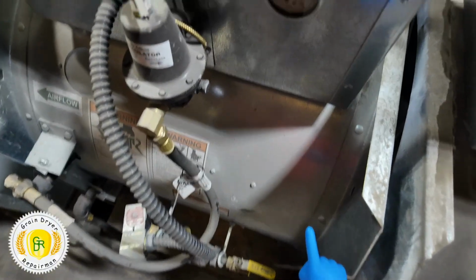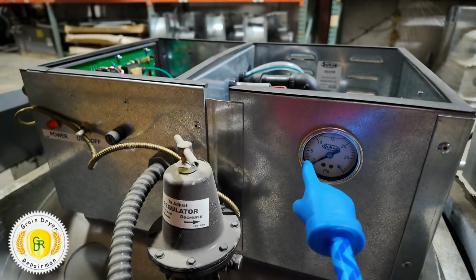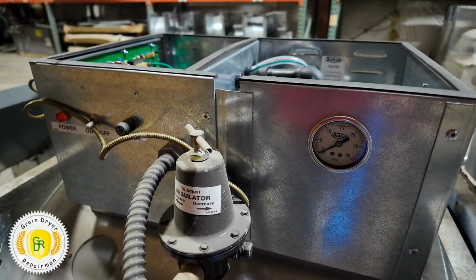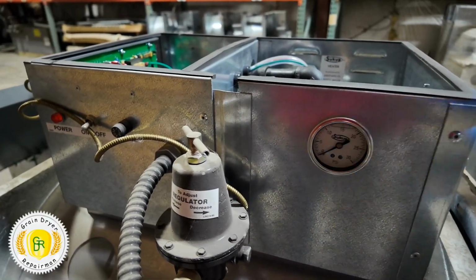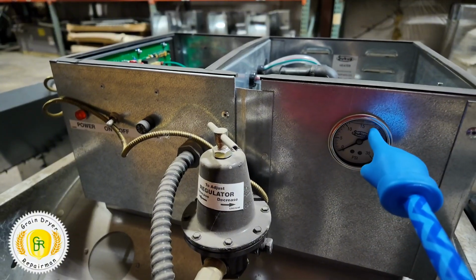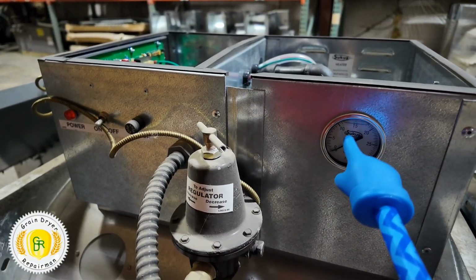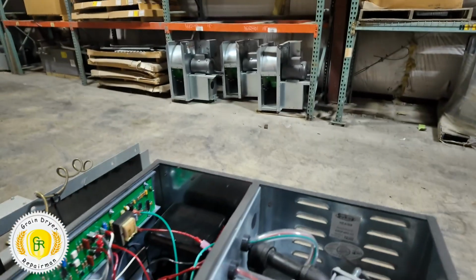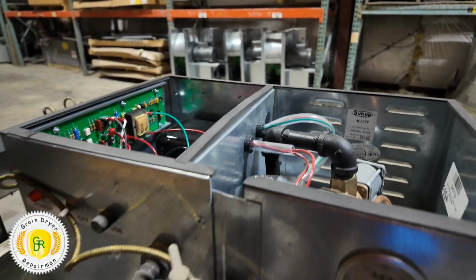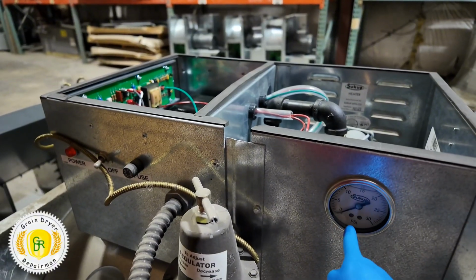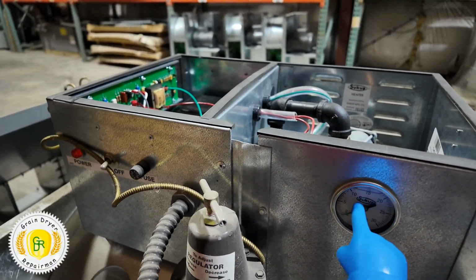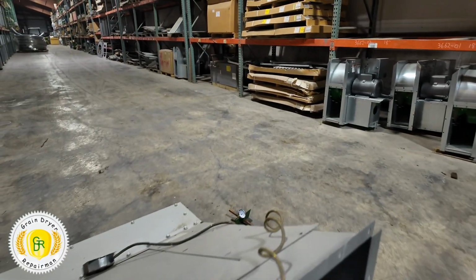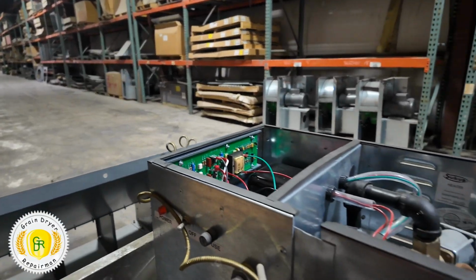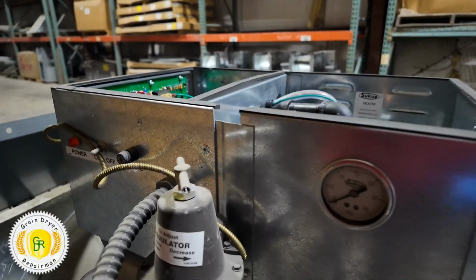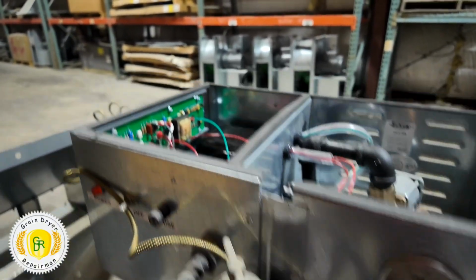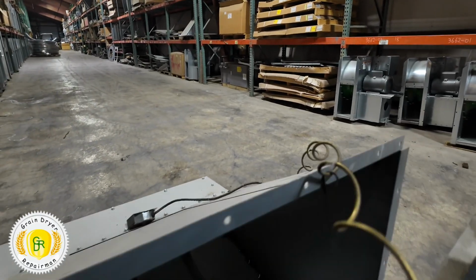What should your gas gauge run? When you first light it and it's not warmer than 80 degrees outside, when you first turn it on, this gauge should go up to 15 pounds or close to there. As it gets warm under the floor, your mod valve is going to start backing off the gas pressure, and this pressure will drop. It does not matter what this gas pressure runs, as long as your temperature is running what it's supposed to run. So this gauge is only for troubleshooting if your temperature is not running correctly.